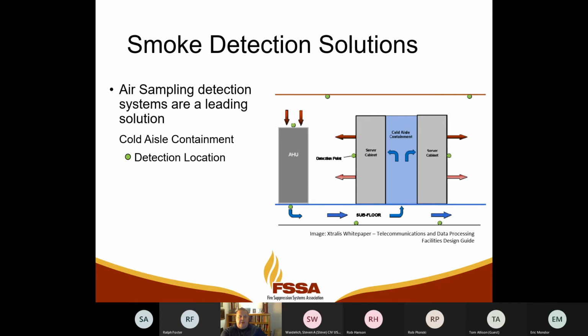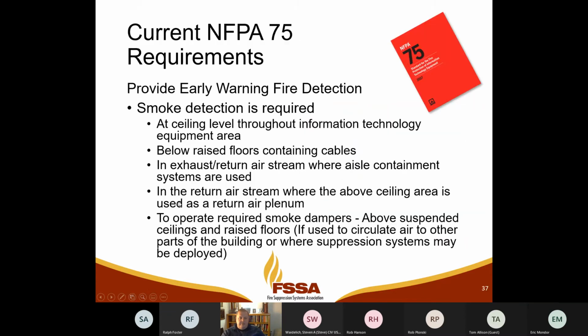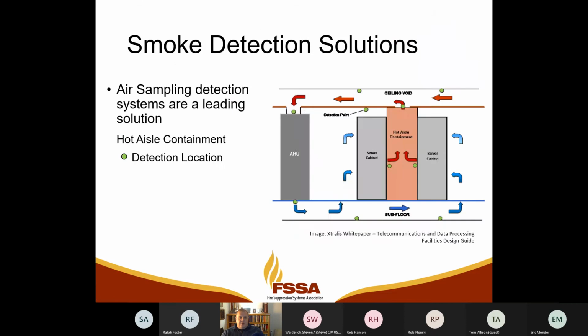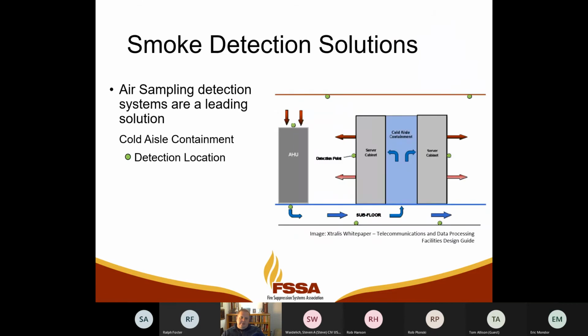This is a cold aisle containment system, so just applying these same smoke detection requirements to cold aisle containment. In the subfloor, if there's cables, as the air leaves the servers, so on the server face, that's a good place to do it. At the ceiling, those are the main three.